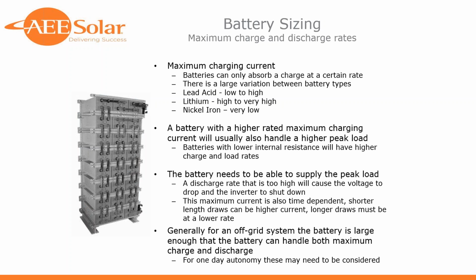We touched real briefly a few slides ago on the need to really take the charge and discharge rates into account, and I think you certainly do a much better job of articulating this than I can. Well, yeah, a battery can only take a certain amount of current before it gets damaged or starts venting gas or overheats. And that is a consideration, particularly not so much for off-grid, because generally the battery is plenty big enough for that. But for backup systems, particularly self-consumption systems to some extent, you do have to watch the sizing of the battery. And different batteries will take different maximum charge currents, and even different lead batteries can take different amounts of charge current. It's not consistent at all.